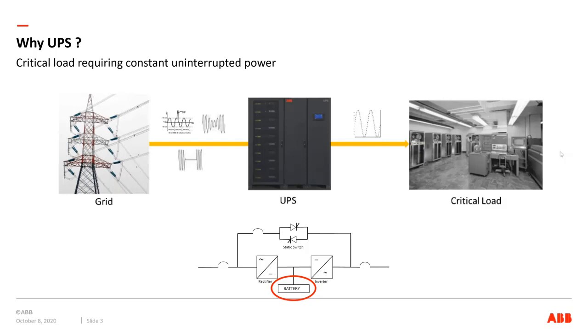And of course, smart UPS people figured out a couple of decades ago that customers want high efficiency. When the UPS is on the static switch, or in what we refer to as bypass, there are very little losses. So this is known as economy mode. The UPS in economy mode is running in bypass in the normal mode, and then it can kick in the inverter in a matter of less than a quarter cycle. So nothing that's critical, but nobody uses it because now they don't have the filter function of the UPS. They still have protection in case of a power failure.